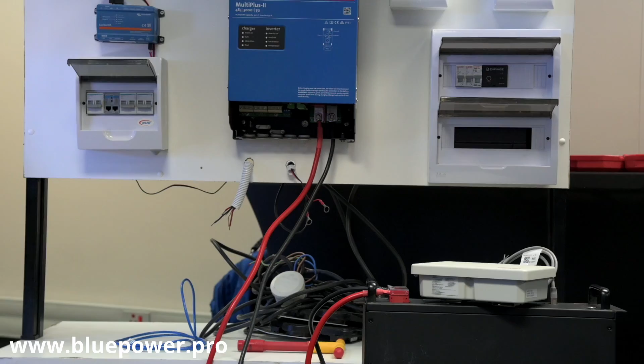It might still not switch on until you connect the BMS type A. BMS type A as well. And then for communication, we've got our specific cable, which is indicated by BYD. This is our BMS type A cable. Battery BMS CAN type A. So to see whichever batteries are compatible and which communication cables they use, we can go onto Google and we can just search Victron Compatibility.